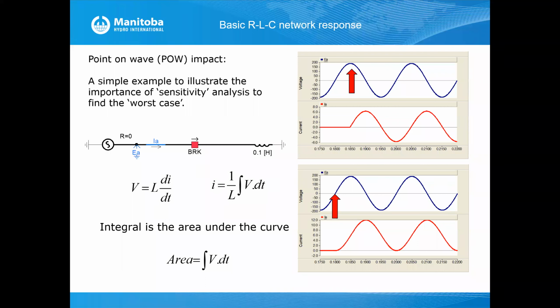So a lot of utilities and engineers typically, for specific studies such as transient recovery voltage, TRV, TOV, switching studies, have to perform a range of sensitivity analysis in order to find out what is the worst operating condition for the study. So what they do is perform a point-on wave study.